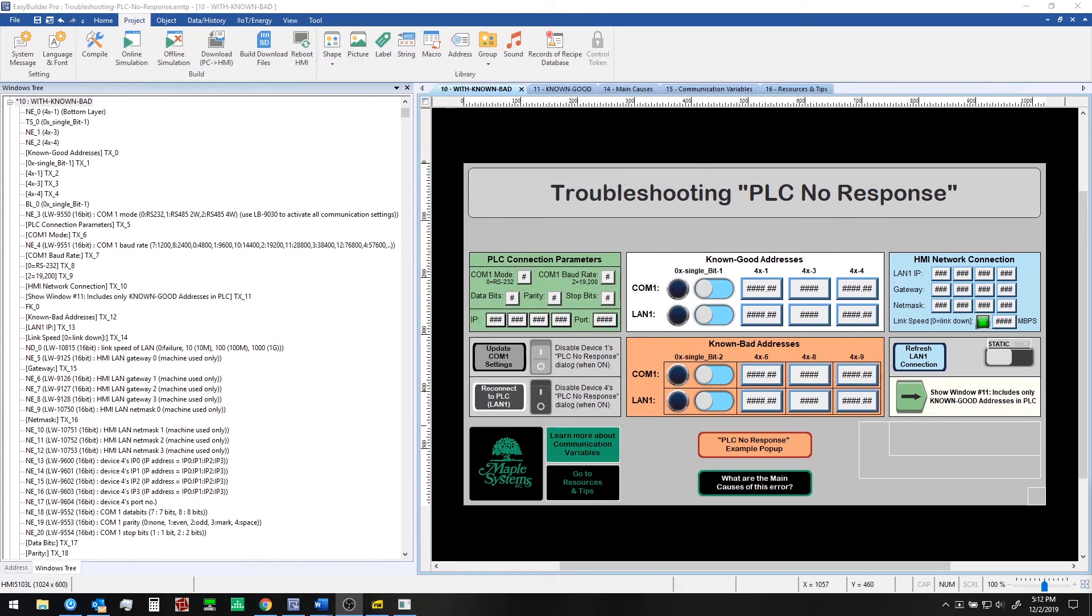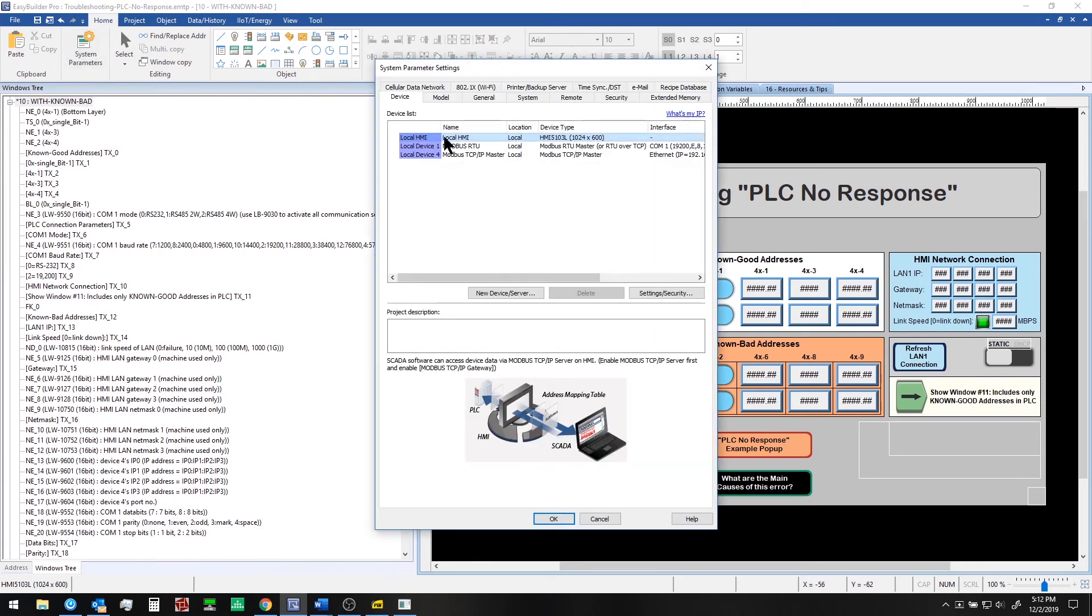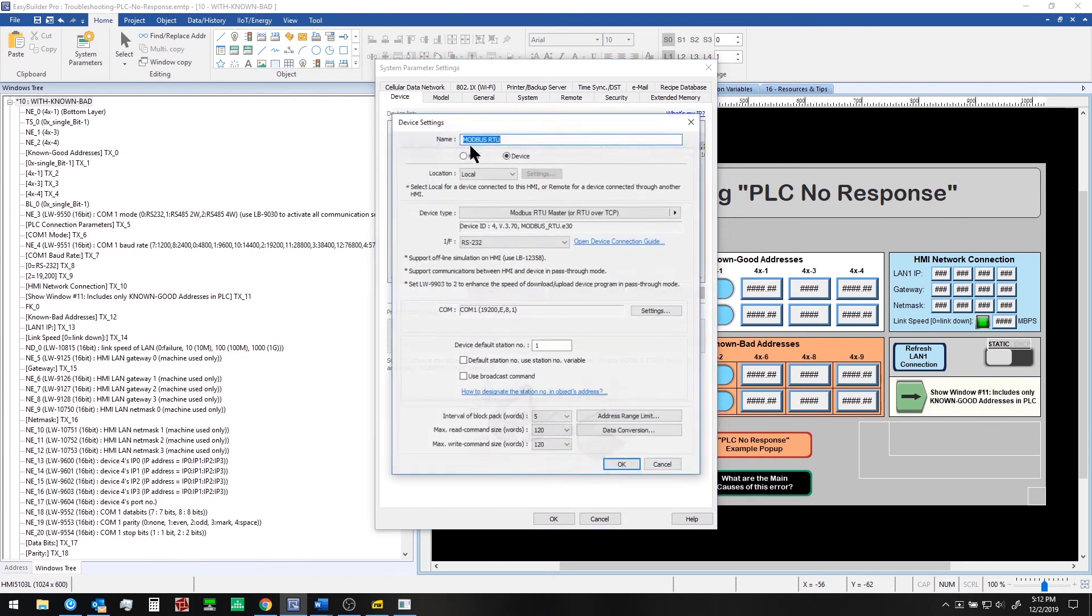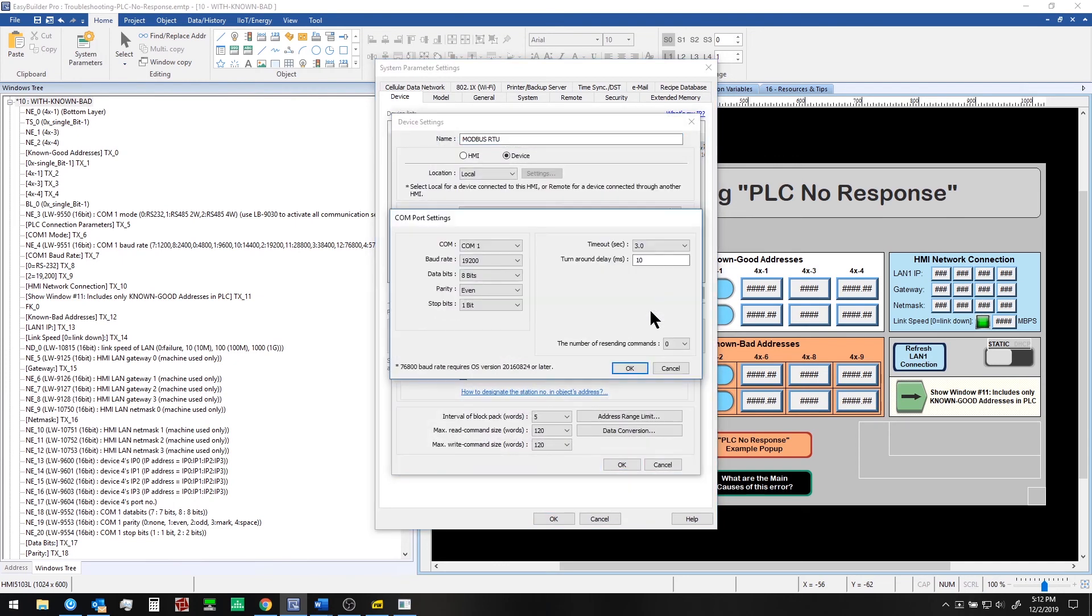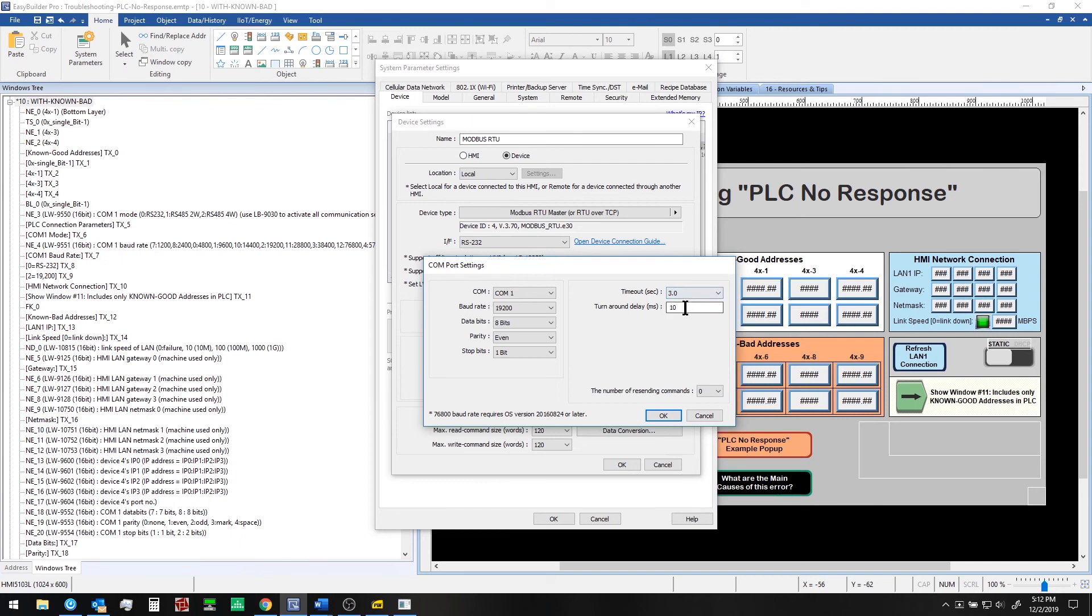And last but not least we have two more settings that you may wish to tune or configure if you're still having issues with communication in your network. So if you go into system parameters for a given device look at the device settings and the communication settings here you have timeout and turnaround delay. Timeout is how long the HMI waits before it alerts you to a failure to communicate with the controller. And turnaround delay if you add this will slow down the polling rate accordingly by a number of milliseconds. So making the HMI wait slightly longer between each poll to the controller or PLC. So in a network with more latency you may wish to modify these settings here as well.